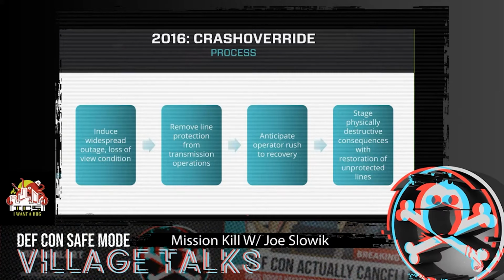So while it didn't work as intended, CRASHOVERRIDE appears as though it was designed to try to achieve physical process destruction within the context of electric transmission operations that would have had disruptive effects lasting potentially months in order to try to restore, recover, and ultimately likely replace damaged gear. And a lot of this comes from knowing both the combination of how the operators in question worked within their environment, as well as the importance of protective relays for electric operations.